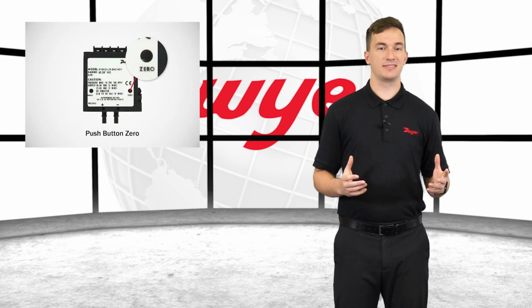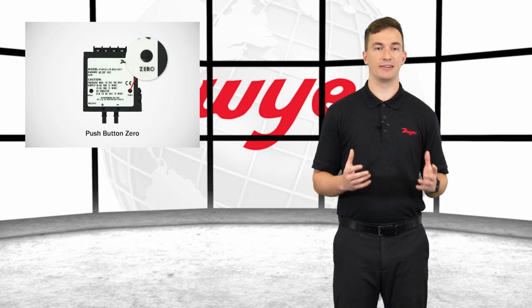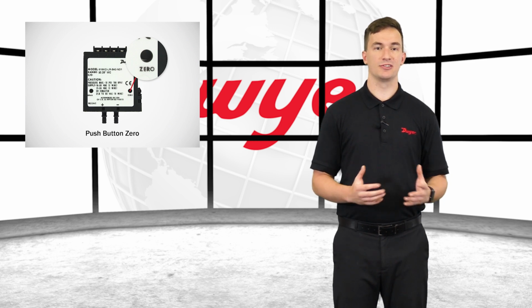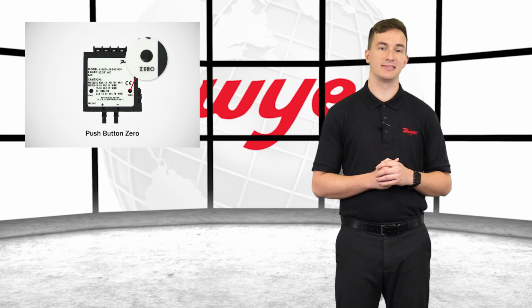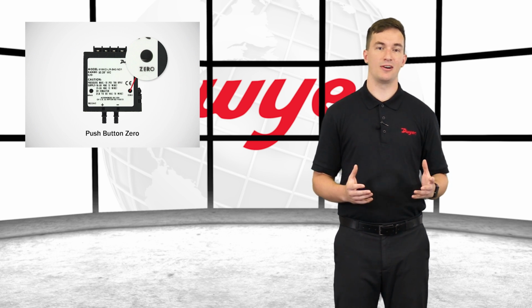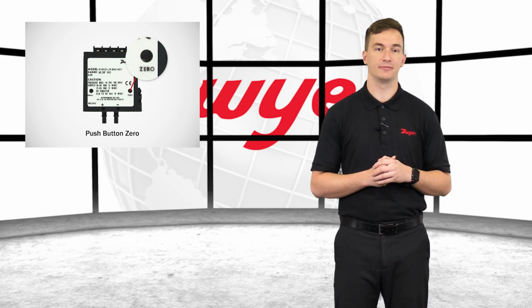The Series 616KD-LR eliminates the need for calibration devices and references by featuring a digital push button for proper calibration of zero. By alleviating cumbersome turn pots, calibration of the instrument can be completed in seconds, saving countless hours installing and maintaining over the service life.